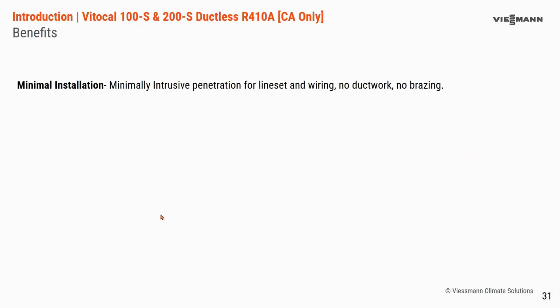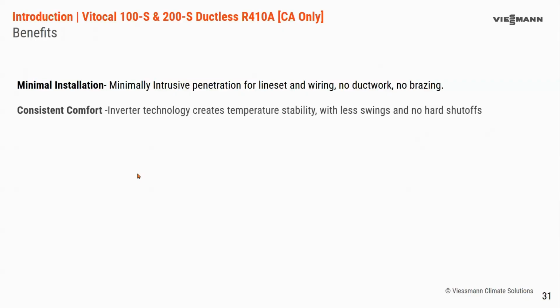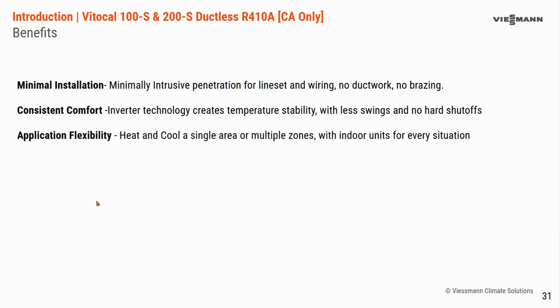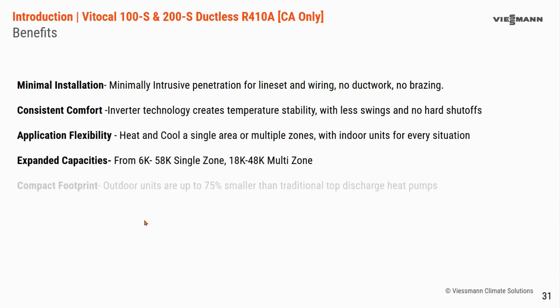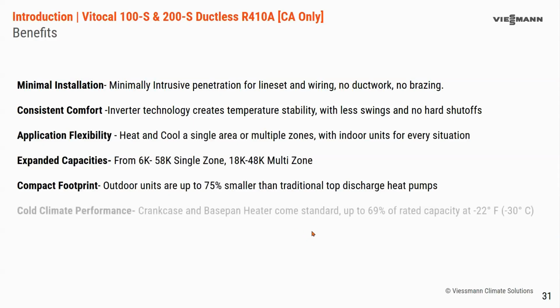So the benefits of the ductless: minimal installation. There's no ductwork required. You don't have to braze. You only really need to make a penetration for your line set and your wiring if there's not already one there. The inverter technology provides a more consistent comfort and also provides energy savings. You have the flexibility with this line to provide heating and cooling in single or multiple zones and with capacities from 6 to 58,000 BTU or up to 4 tons in a multi-zone. And the outdoor units, you save up to 75% footprint versus a top discharge heat pump, so a traditional heat pump. And we have cold climate performance with up to 70% nearly at -30°C. Depending on which unit you select, we have upwards of above 100% capacity at 5 degrees Fahrenheit, I believe it's -15°C.